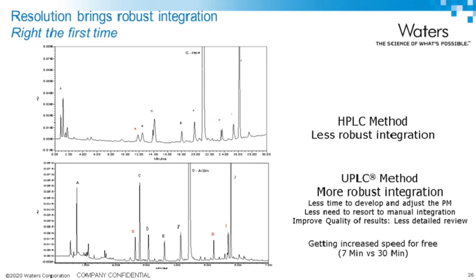And I just wanted to share a chromatogram. This is a method that we took from HPLC, which runs in about 30 minutes, to a 7-minute UPLC method. But from my point of view, from a data integrity standpoint, the peaks are so much easier to integrate in the second example. Yes, you get a 7-minute run instead of a 30-minute run, but what's most important is I can absolutely confidently integrate the areas of those peaks, separate them from the peaks nearby, and have an automated method, which means as an analyst, I don't need to step in and make changes to the parameters in order to get accurate integration of those peaks. And that gives me a lot of confidence about right-first-time peak integration.